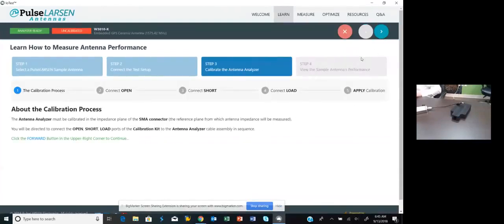Now I'm going to calibrate the antenna analyzer. It is very important to always calibrate your antenna analyzer whenever you're using it, especially when you switch frequency ranges if you're using it for more than one thing. This is what tells the antenna analyzer where to consider the end of its 50 ohm transmission line, as described in the presentation. So this calibration is very critical to make sure you get accurate results from that point on, so we can measure return loss from this point on, because of course everything radiates. So it's important for it to establish a point: this is where I should recognize the beginning of where I need to measure power loss, that kind of thing.